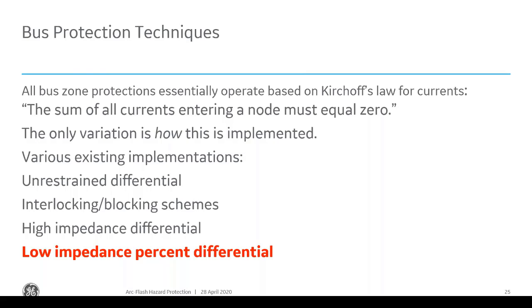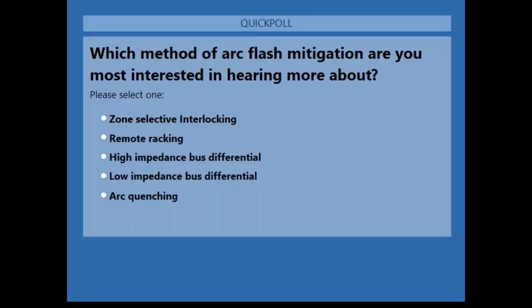So I'll just leave it at this: high impedance is basically, again, just like the overcurrent, but more secure, where the CTs are all paralleled together. If there's an external fault, the current circulates in the external circuit. It doesn't go into the circuit of the relay. If there's an internal fault, the current goes into the circuit of the relay. It can be very sensitive, unlike the overcurrent. And as I said, unlike the overcurrent, it's very secure. And it's a proven technique we've used for a long time before we started using low impedance percent differential.